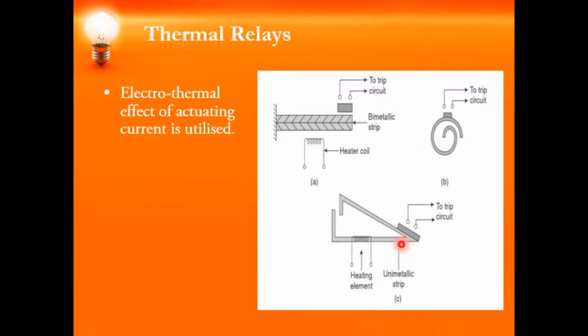For the protection of a three-phase motor, three bimetallic strips are used. They are energized by the currents from the three phases. Their contacts are arranged in such a way that if one of the spirals moves differently from the others due to an unbalance which exceeds 12%, their contacts meet and cause the circuit breakers to trip. These spirals also protect the motor against overloading.